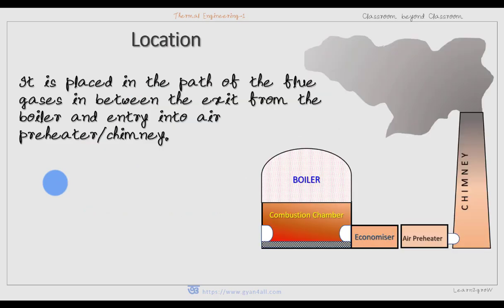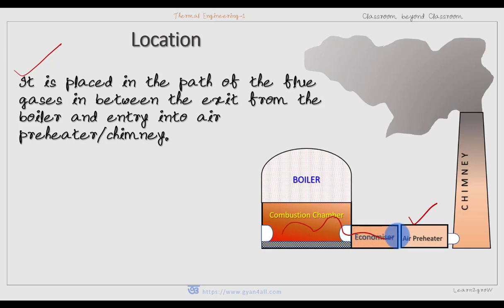Now, the question is: what should be the location or position of the economizer? It is placed in the path of the flue gases, in between the exit from the boiler and the entry to the air preheater. If an air preheater is used, the economizer is placed before the air preheater. If there is no air preheater, then the economizer is positioned between the chimney and the exit of the combustion chamber.